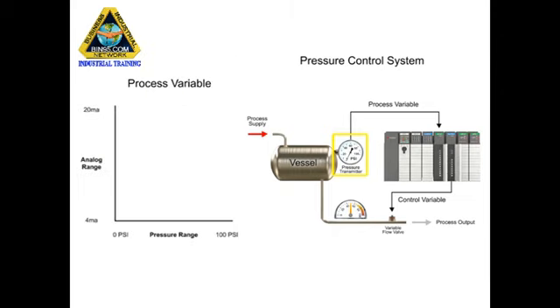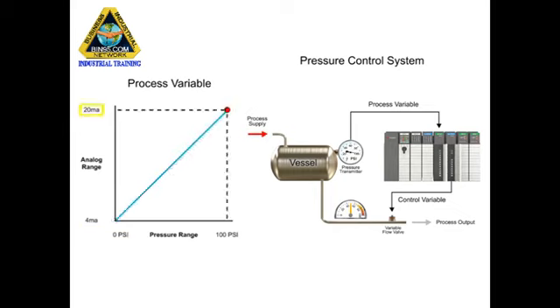The pressure transmitter, identified as the process variable, converts 0 to 100 psi to a 4 to 20 milliamp signal. With a linear relationship, 0 psi measured at the transmitter produces a 4 milliamp signal, and at 100 psi a 20 milliamp signal is produced.